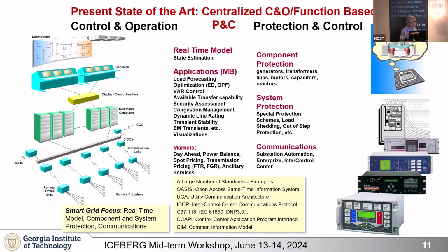That is, even if we use protective relays to provide the SCADA, the protective relays have the capability to provide the data much faster than the SCADA rates. SCADA rates are in the order of 1 to a few seconds. Okay? But still, we reprogram the relays to provide the data at the rates of the SCADA system. Okay? So which is underutilization of this activity.